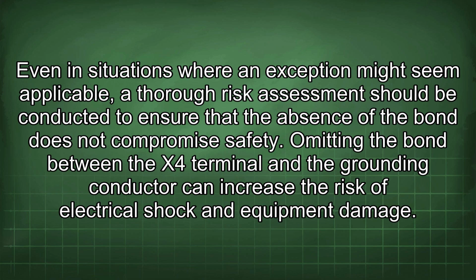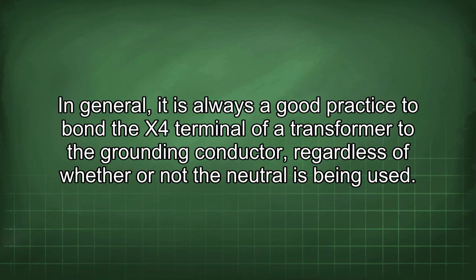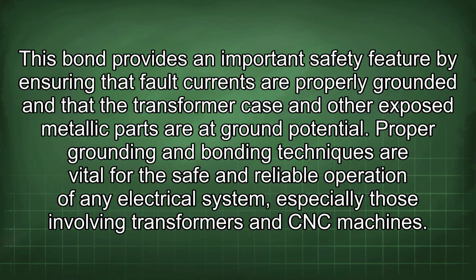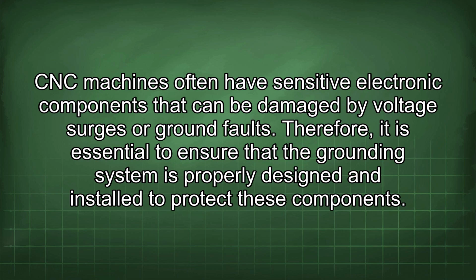Omitting the bond between the X4 terminal and the grounding conductor can increase the risk of electrical shock and equipment damage. In general, it is always a good practice to bond the X4 terminal of a transformer to the grounding conductor, regardless of whether or not the neutral is being used. This bond provides an important safety feature by ensuring that fault currents are properly grounded and that the transformer case and other exposed metallic parts are at ground potential. Proper grounding and bonding techniques are vital for the safe and reliable operation of any electrical system, especially those involving transformers and CNC machines. CNC machines often have sensitive electronic components that can be damaged by voltage surges or ground faults. Therefore, it is essential to ensure that the grounding system is properly designed and installed to protect these components.